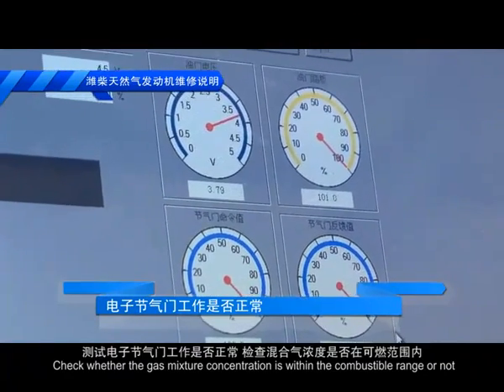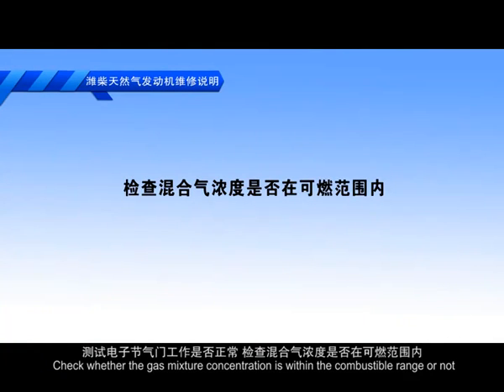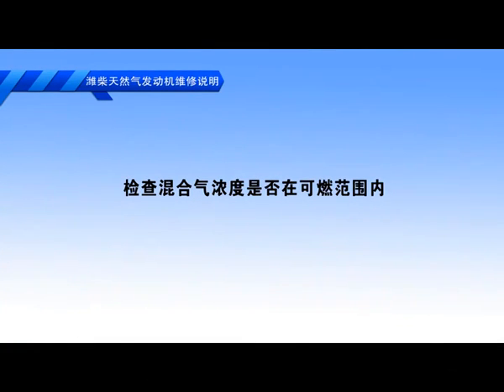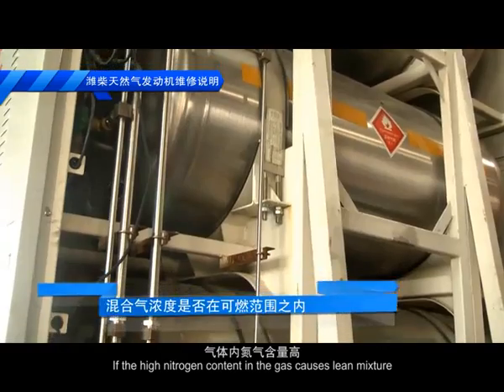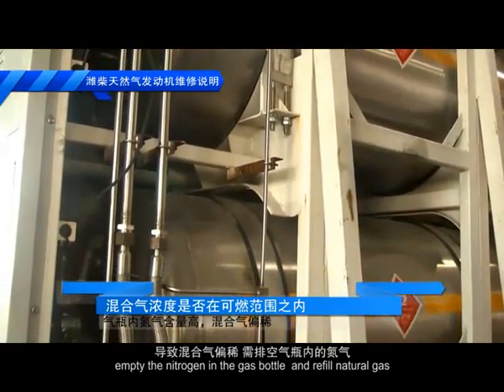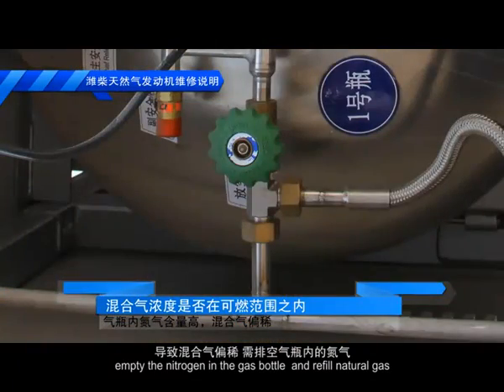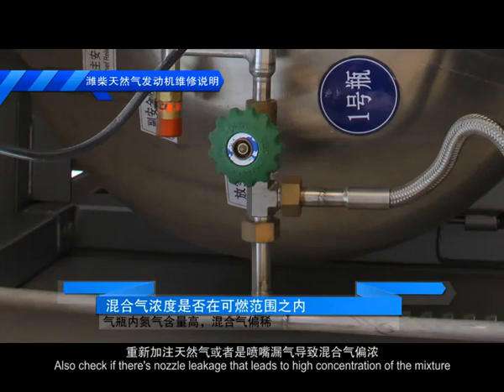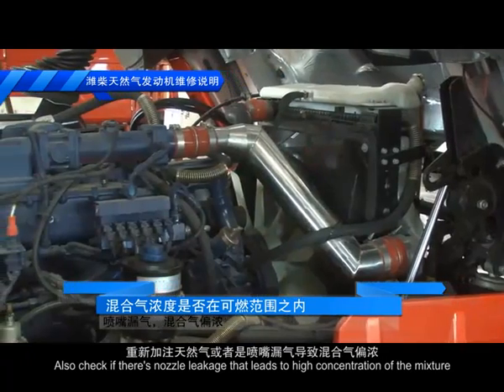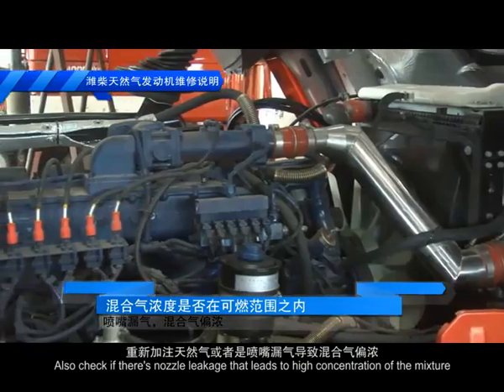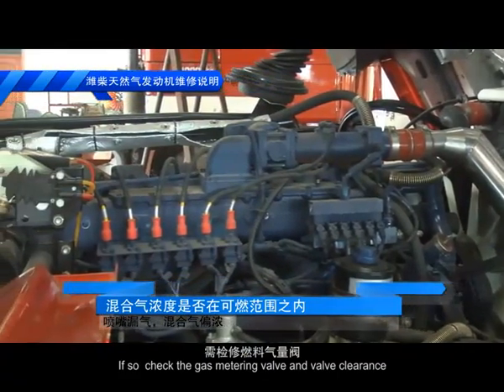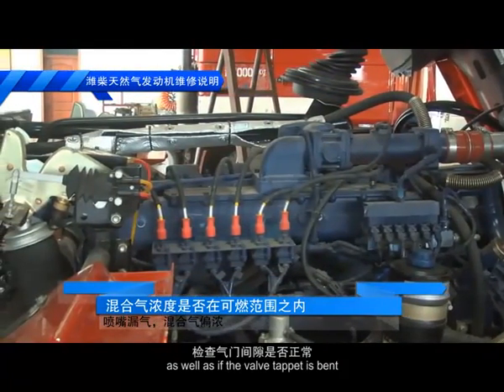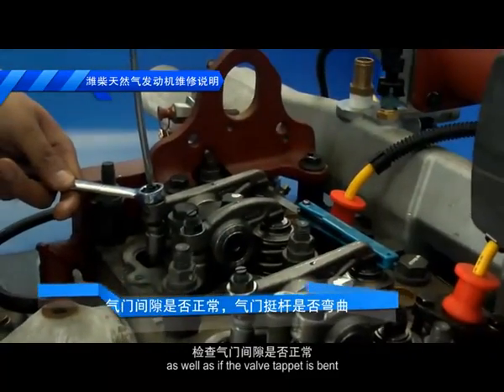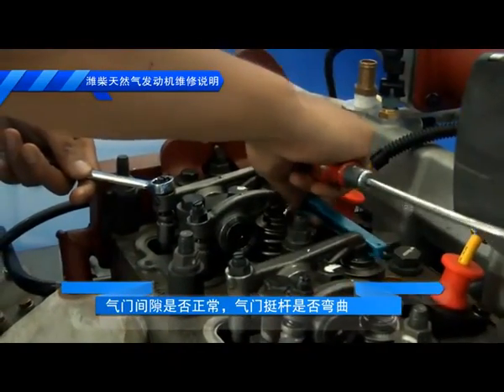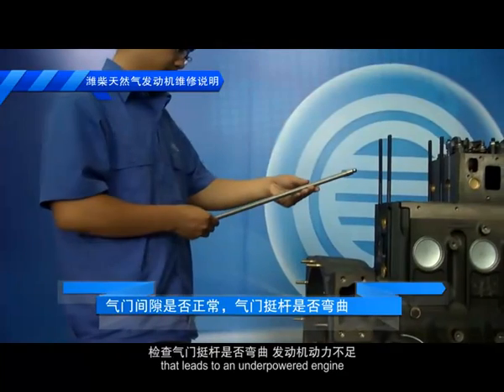Check whether the gas mixture concentration is within the combustible range or not. If the high nitrogen content of the gas causes a lean mixture, empty the nitrogen in the gas bottle and refill the natural gas. Also, check if there is nozzle leakage that leads to a high concentration of the mixture. If so, check the gas metering valve and valve clearance, as well as whether the valve tappet is bent, which leads to an underpowered engine.